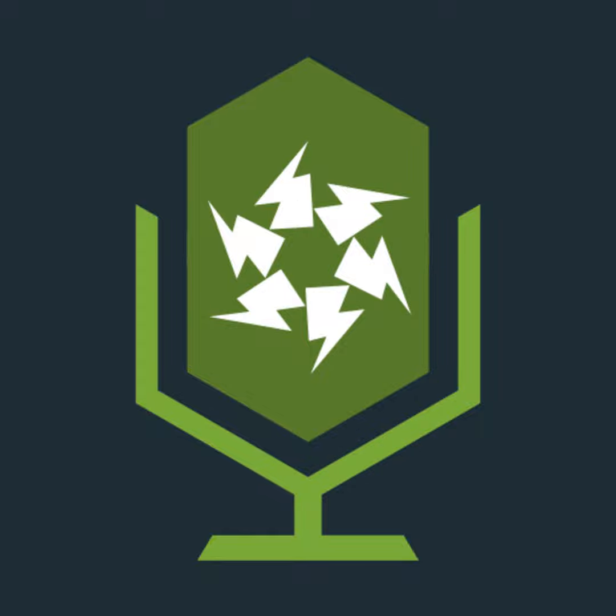So a couple of things we need to consider. We need to consider ambient air temperature. The cable's current carrying capacities in Appendix 4 are given at 30 degrees as the ambient. If we were to say a cable can carry 27 amp at 30 degree ambient, if we then installed it at a constant temperature of 35 degrees, it's obviously going to be a little bit less because it's a little bit warmer. Similarly with grouping, we've got to consider if the cable's going to be grouped with others.